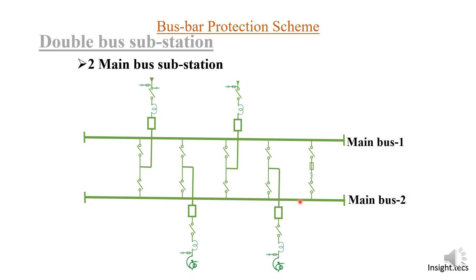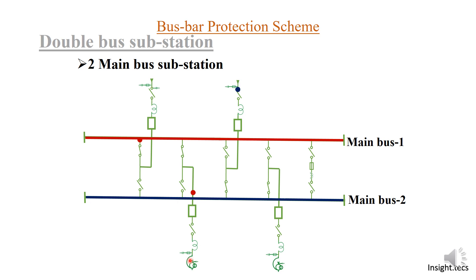The bus coupler connects both buses when both isolators are on. For example, if we want to connect a feeder to bus one, bus one isolator is closed and power flows through bus one. If you want to connect the feeder to bus two, that isolator is closed and bus two is selected. For a transformer bay, when bus one isolator is closed the transformer operates on bus one, and for the other transformer it operates on bus two. Power flow will follow accordingly through the selected bus and transformer.